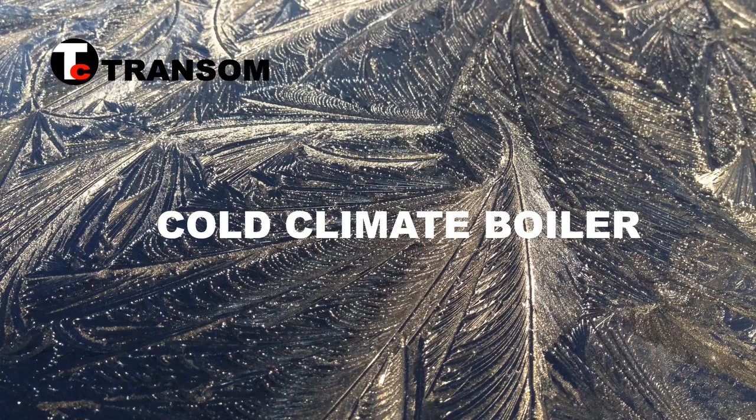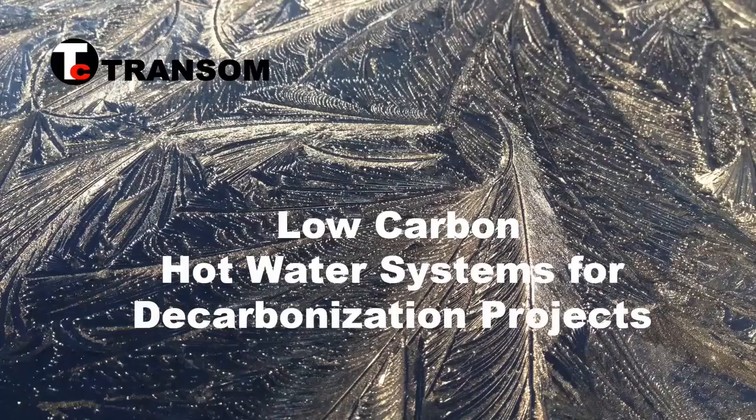Yeah. So we're here to talk about the air source replacement for boilers at very low temperatures and reaching full temperatures, so you can retain the piping and radiators and fan coils and so on that's existing in a building, so it becomes a component replacement project as opposed to a system replacement project. So doing that, and cold climate boilers is one name. Another one is low carbon hot water systems for decarbonization projects, which is a mouthful.